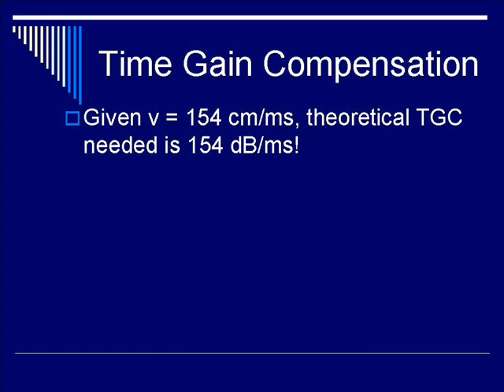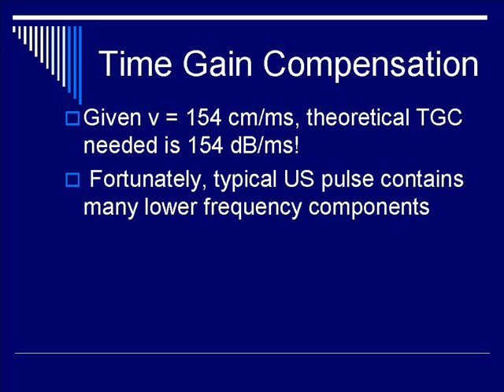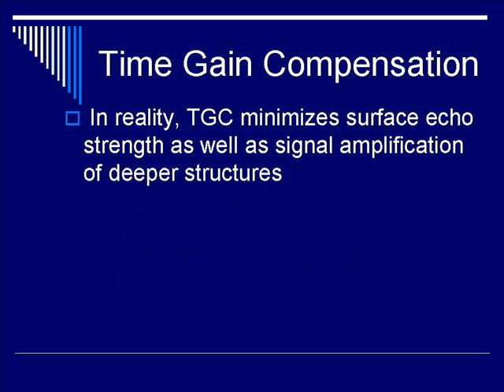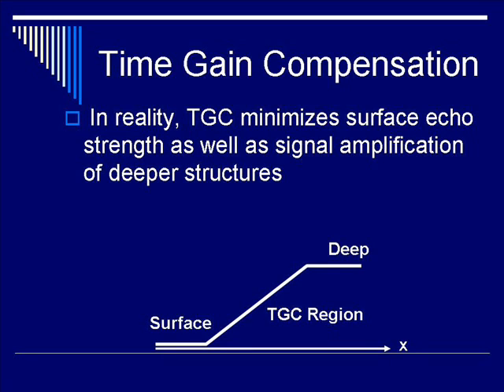Specifically, let's talk about time gain compensation. In principle, since the velocity of sound is 154 cm per ms, if there is 1 dB per cm loss in amplitude, the theoretical time gain needs to be 154 dB per ms. Fortunately, a typical ultrasound pulse contains many lower frequency components, which do not require as much compensation as theoretically expected. Also, lower velocity tissues such as fat lessen the compensation requirements as well. In reality, TGC minimizes surface echo strength as well as signal amplification of deeper structures, such that you get a characteristic curve.